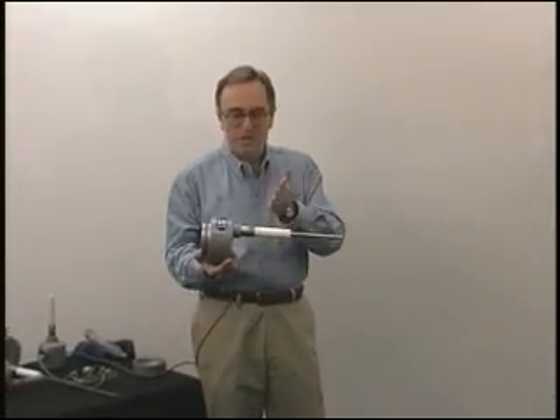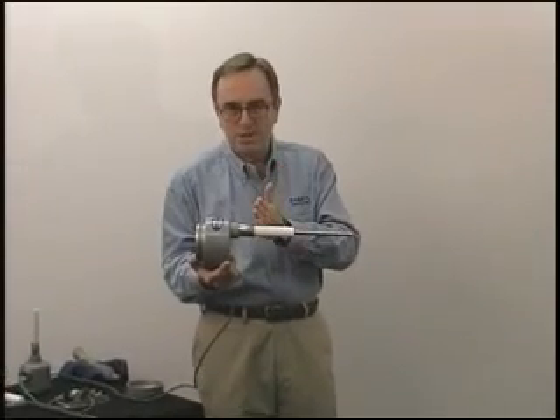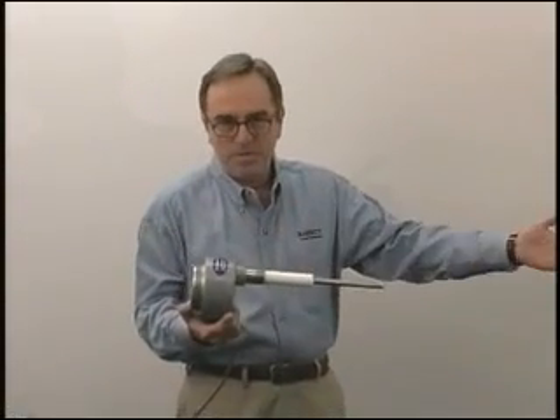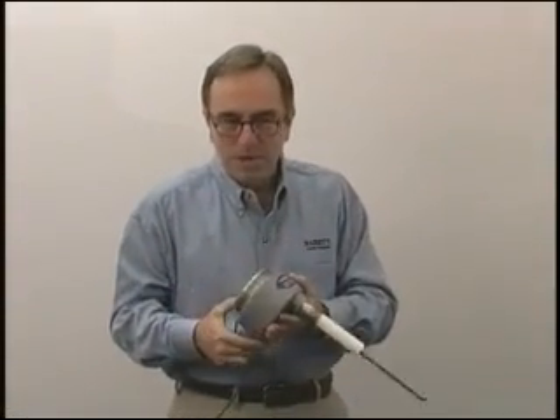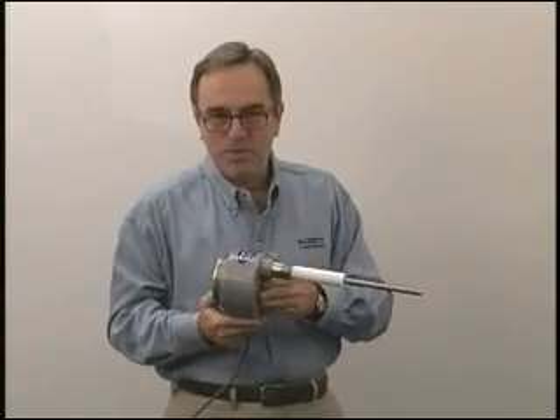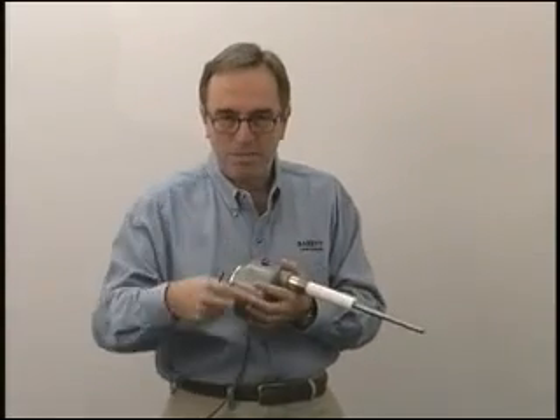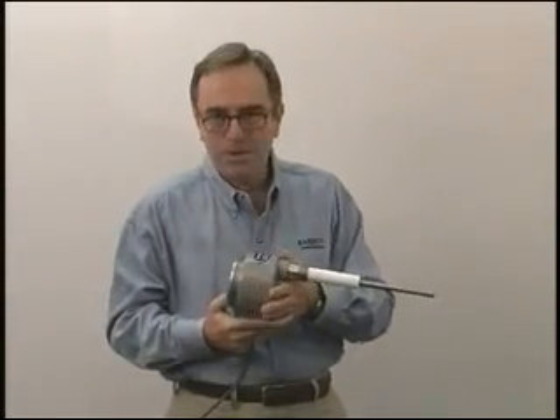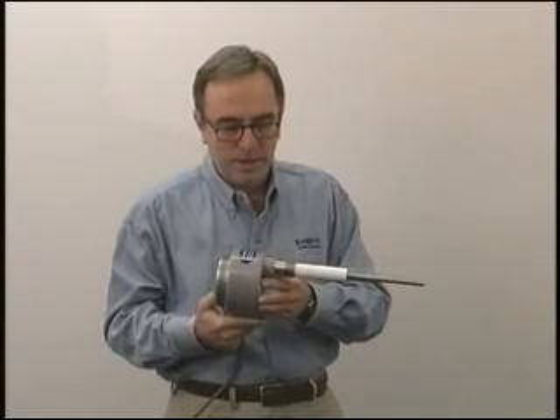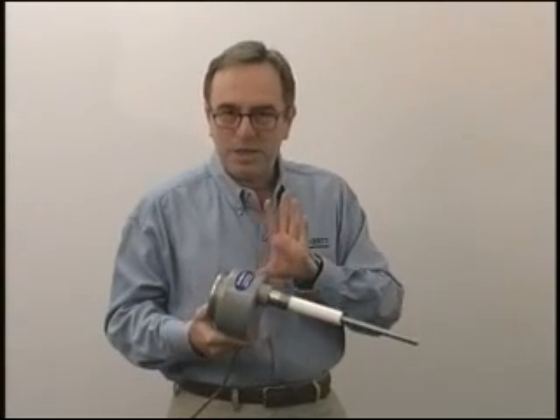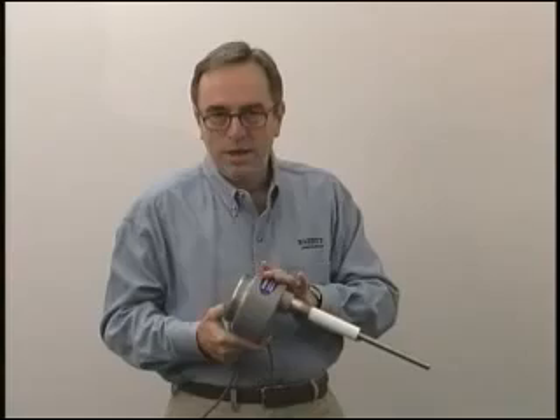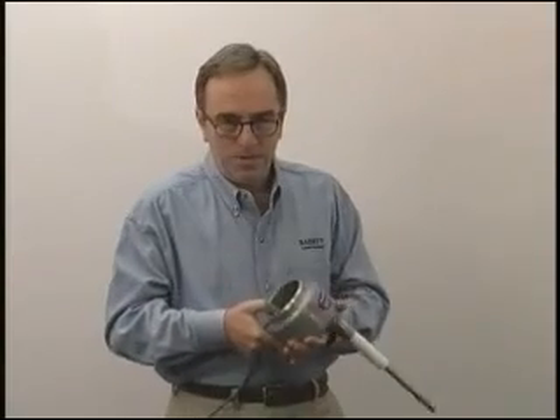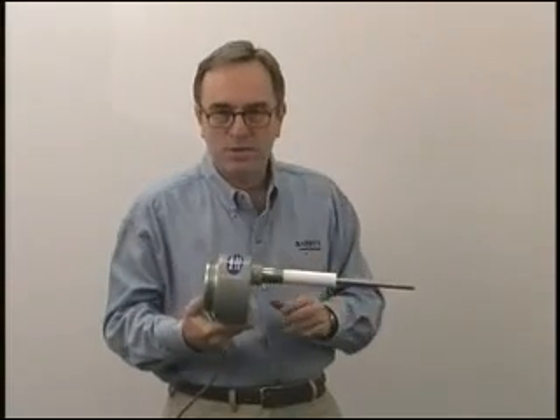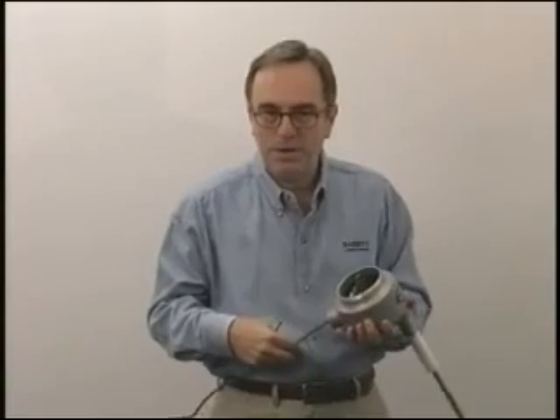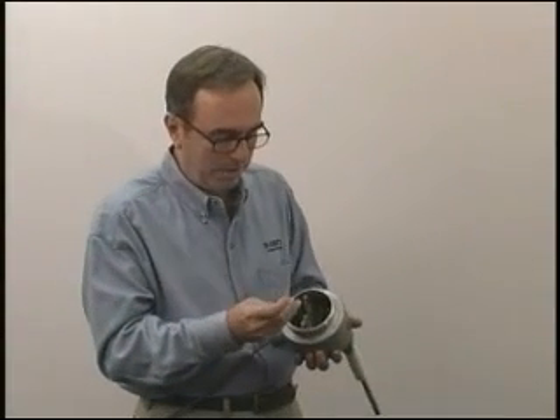That's why these electronics will power a probe from a fraction of an inch long to over 150 feet long. By the way, this unit is a direct retrofit for a rotating paddle type unit, frequently used for dry bulk solids. It has the same exact control wiring, so it's out with the old, in with the new. There's no moving parts in the vessel, no paddles to fall off, bearings to wear out, or motors to burn up.